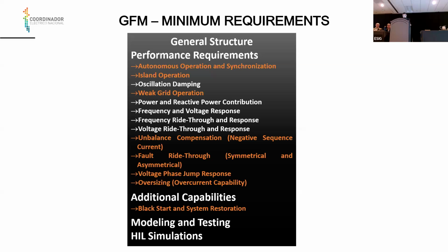In addition to the core capabilities already known for us, we incorporate the black start and system restoration. This has been particularly important after the blackout event that we had earlier this year, where the black start and system restoration was not so optimal. The document ends with our results on modeling and testing by us about this grid forming requirement, and we present the hardware-in-the-loop simulation results.